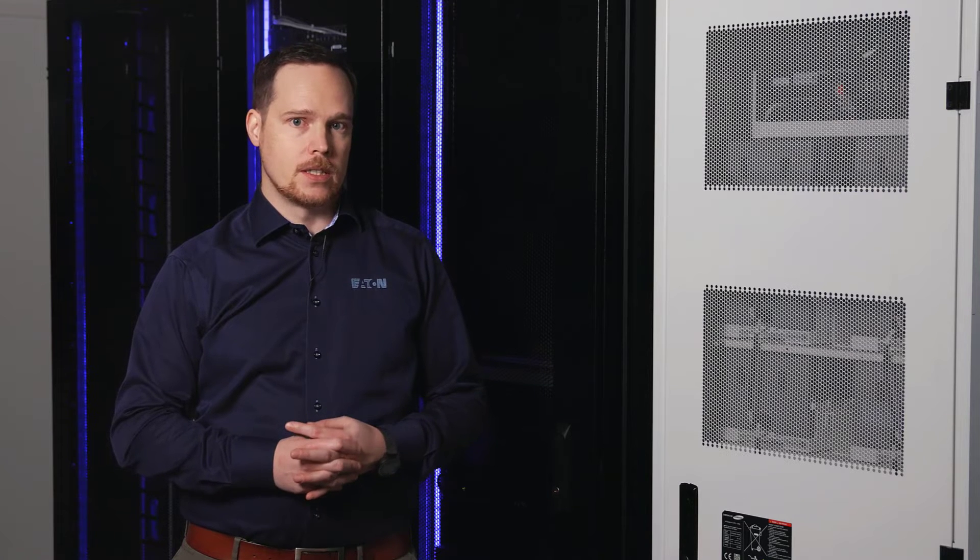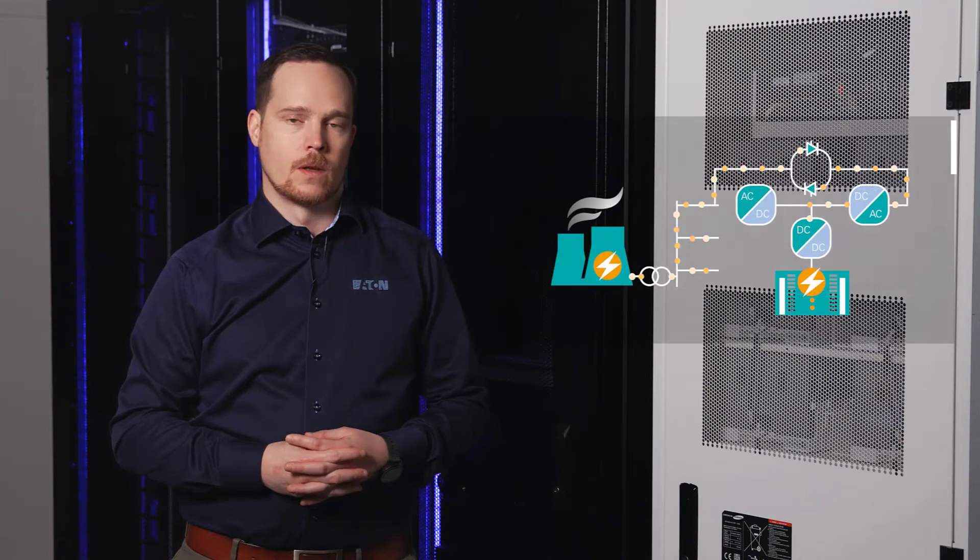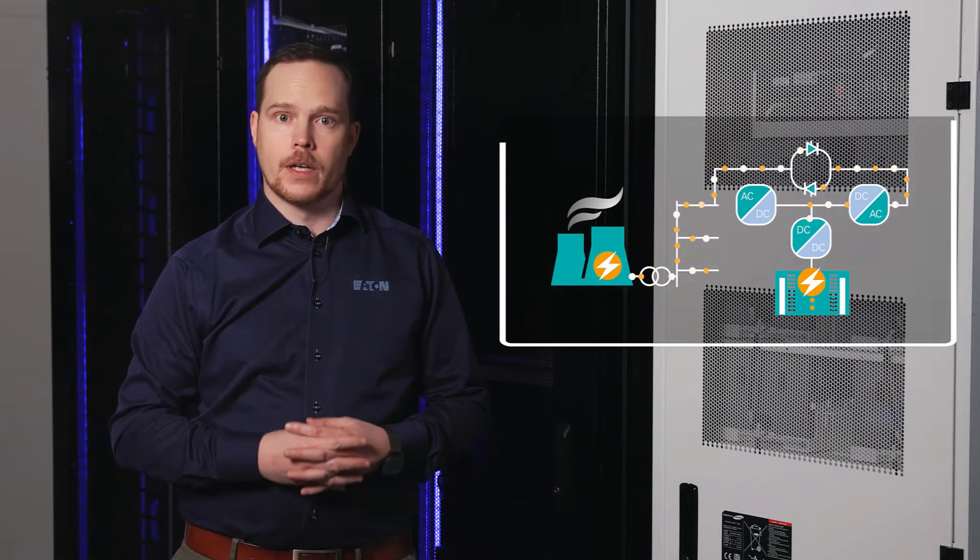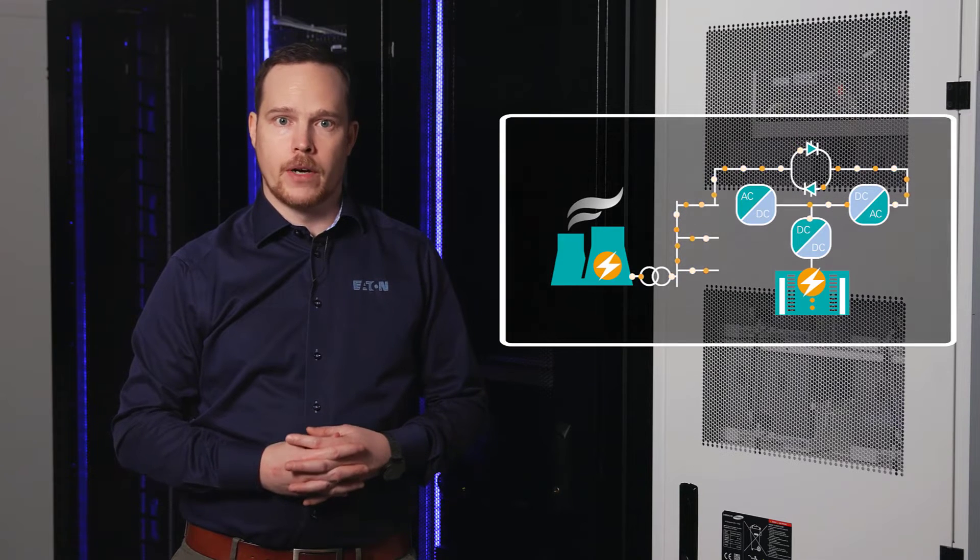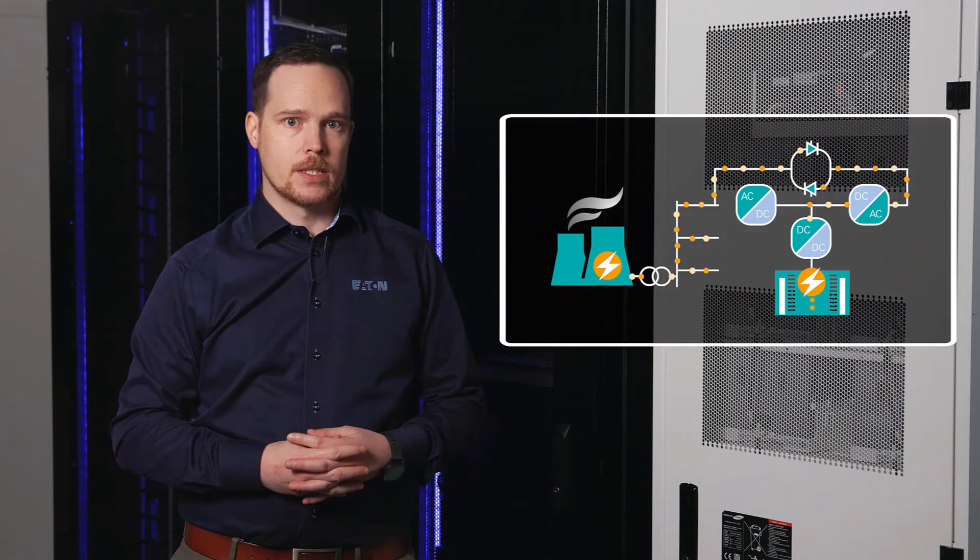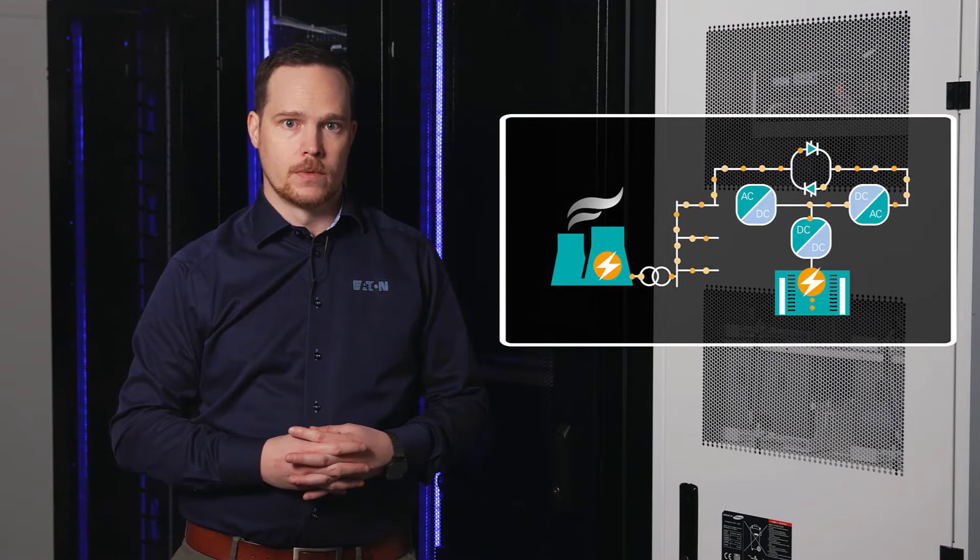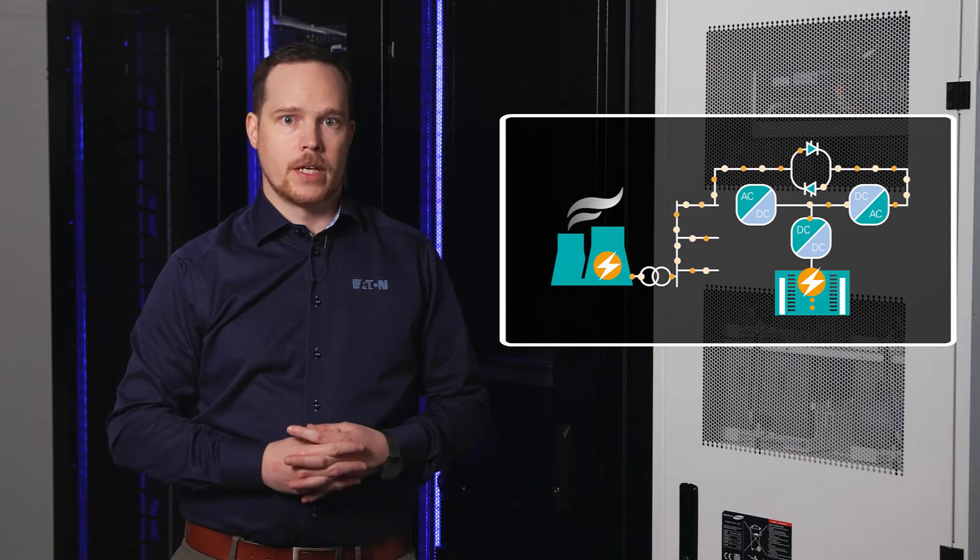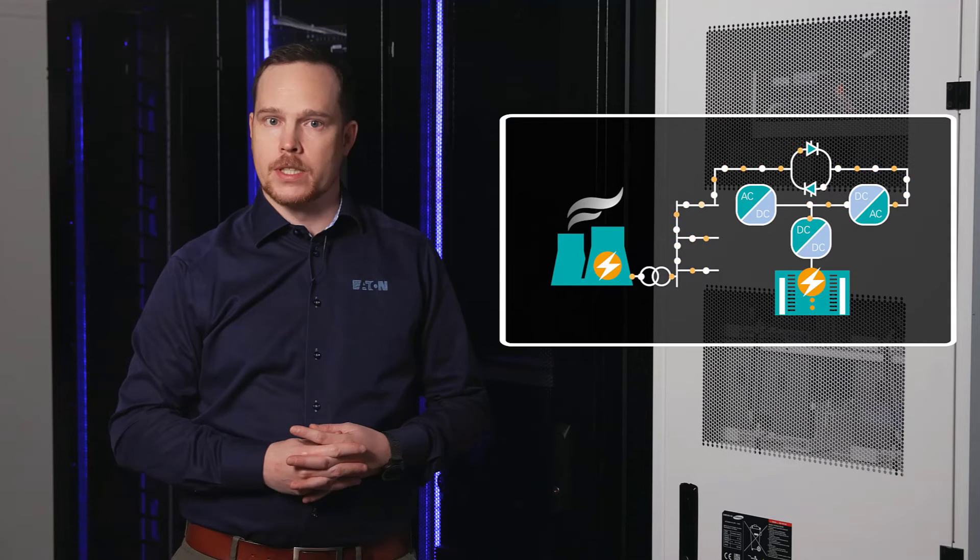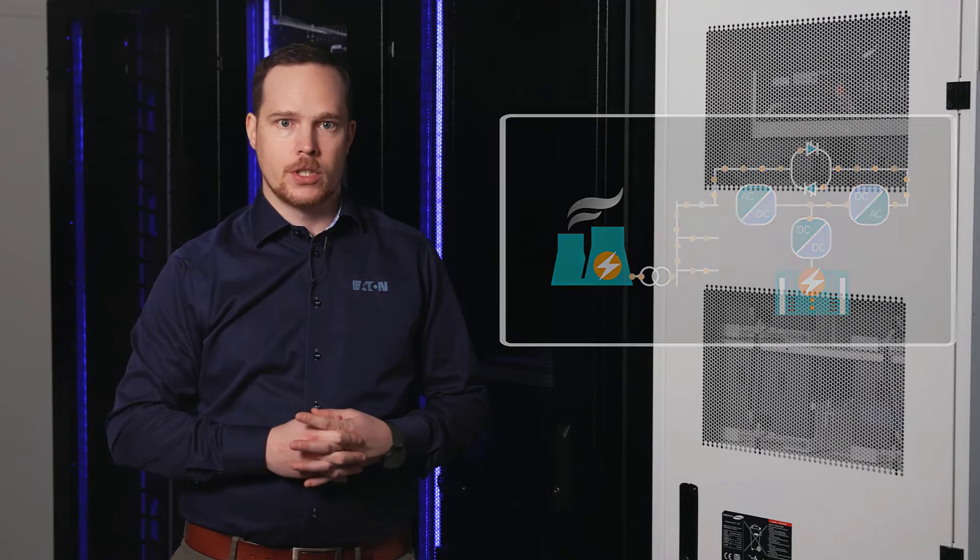In ECT, we feed power through the UPS and back to the input through the static bypass line. This power can then feed parallel UPSs supporting the load. This makes battery testing much easier to coordinate and saves a lot of money. All you need is an Eaton service technician on site.